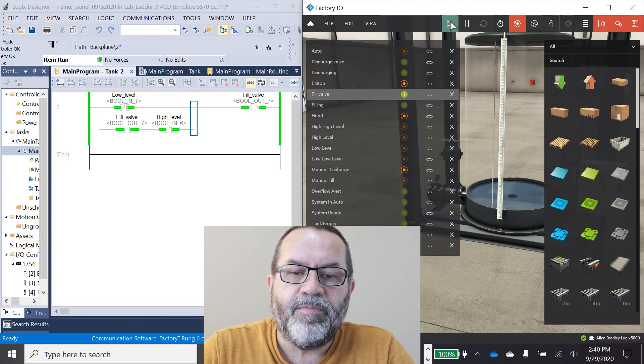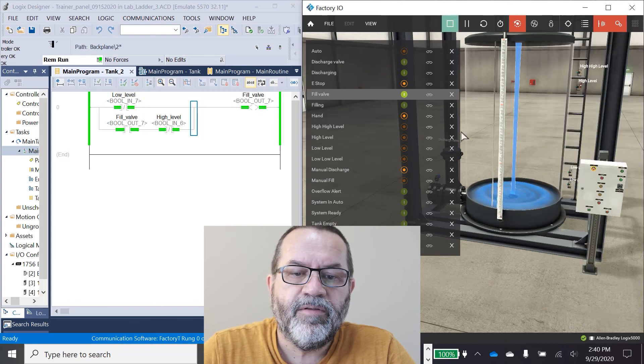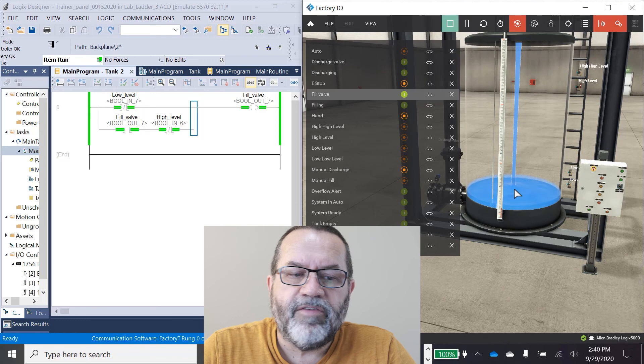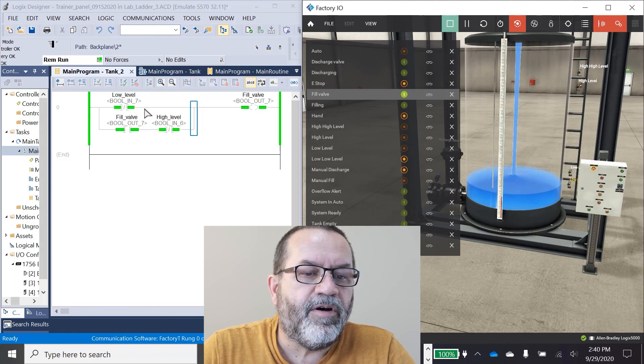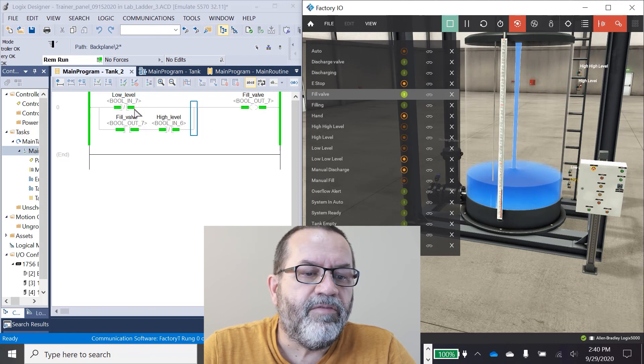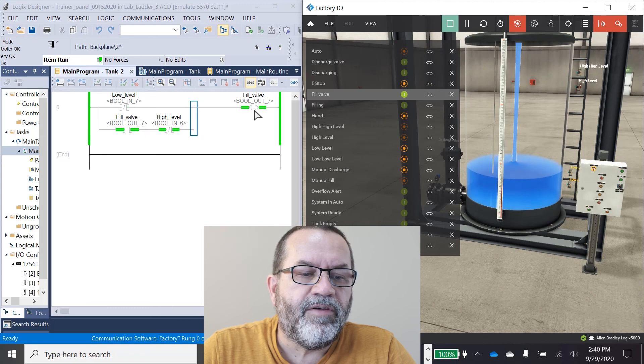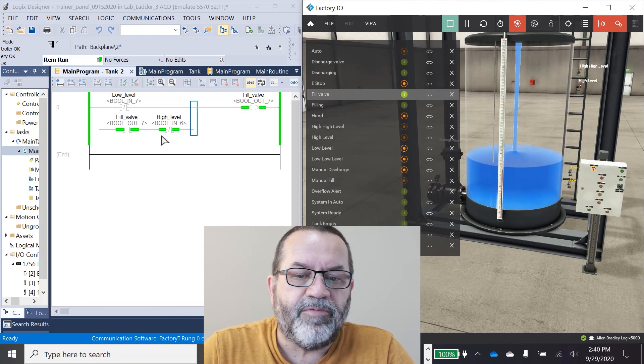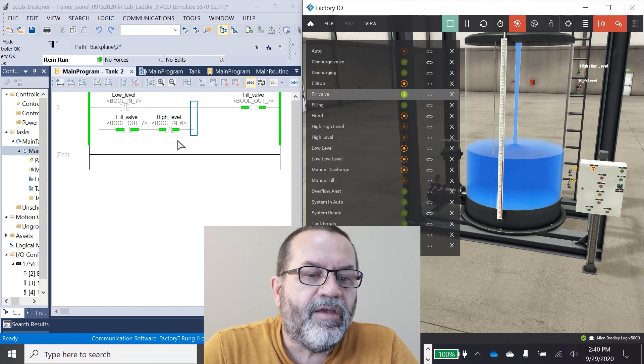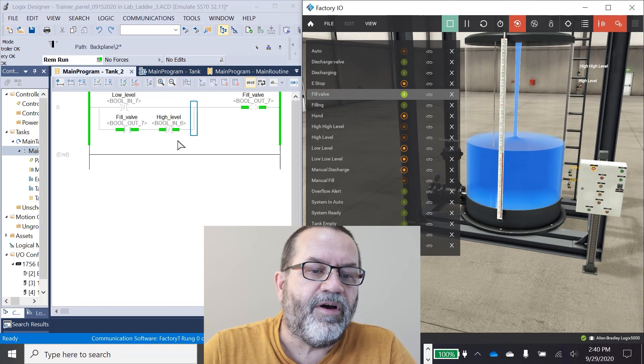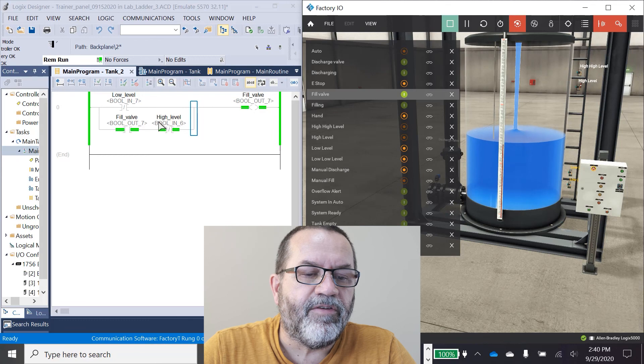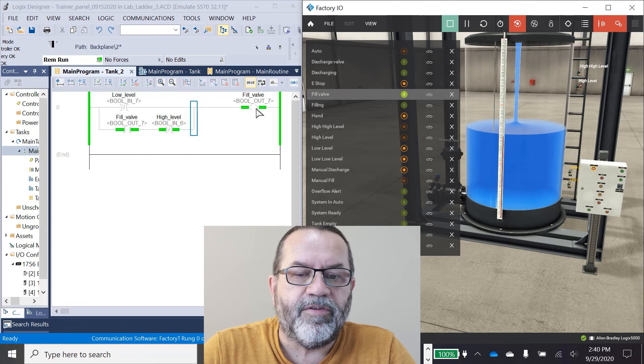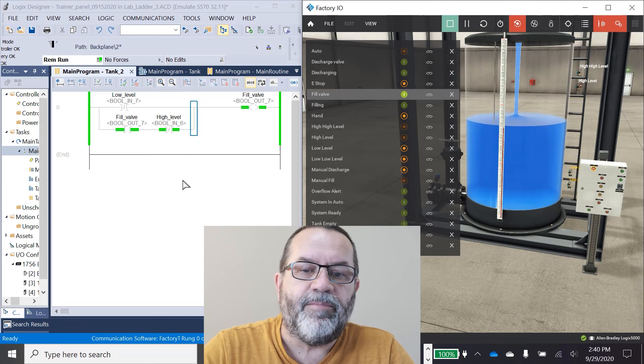And I'll go back into run mode. Now the tank's going to start filling. So you've got low level hot, and even when it goes cold, the fill valve is going to keep filling because it's sealed itself in. And then I'm going to break that seal with a high level switch. So when this guy goes cold, the seal is going to break and the fill will stop.